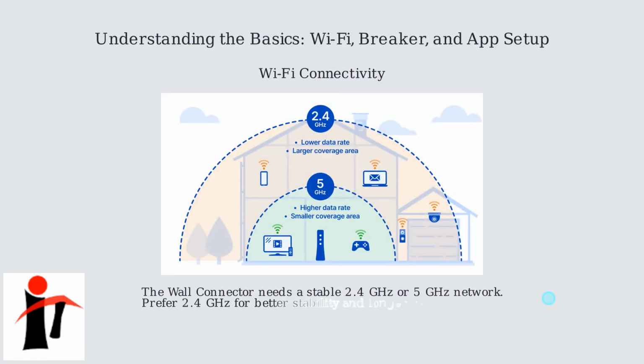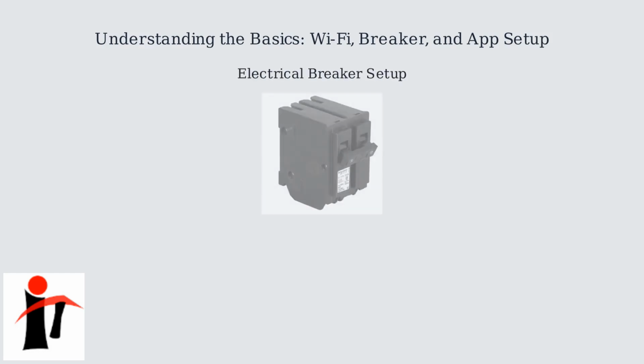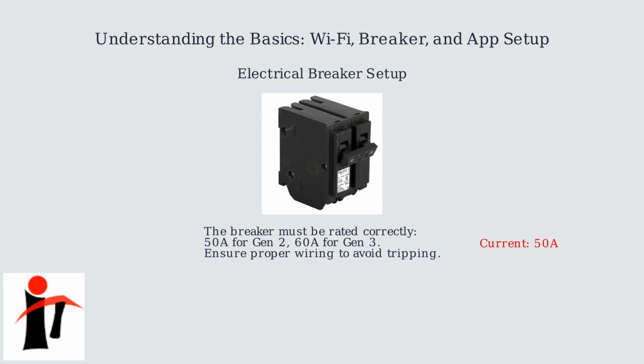The Tesla wall connector relies on a stable Wi-Fi connection for its smart features. It can connect to either a 2.4 GHz or 5 GHz network, but we recommend 2.4 GHz for better stability and longer range. Your electrical breaker must also be correctly rated and wired. For Gen 2 wall connectors, use a 50 amp breaker. For Gen 3, you'll need a 60 amp breaker to handle the load safely.